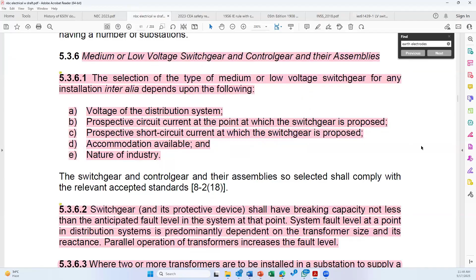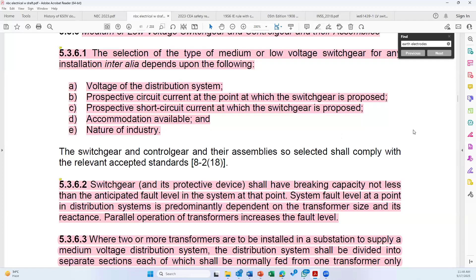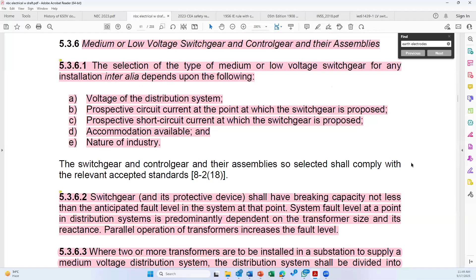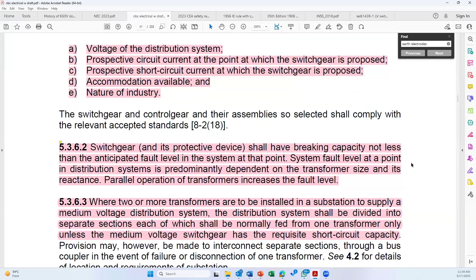Now, if this 5.3.6.1 gives only 5 items in the list, what happens is generally we misread. We say that, okay, only 5 items are required. Why do I fill up this entire table? So ideally, in a standard, instead of giving these 5 items, it should have said that for every switchgear or control gear assembly, the electrical designer shall provide the filled Annex C to the manufacturer of the control gear assembly, or the protective devices shall be selected based on this particular Annex C.